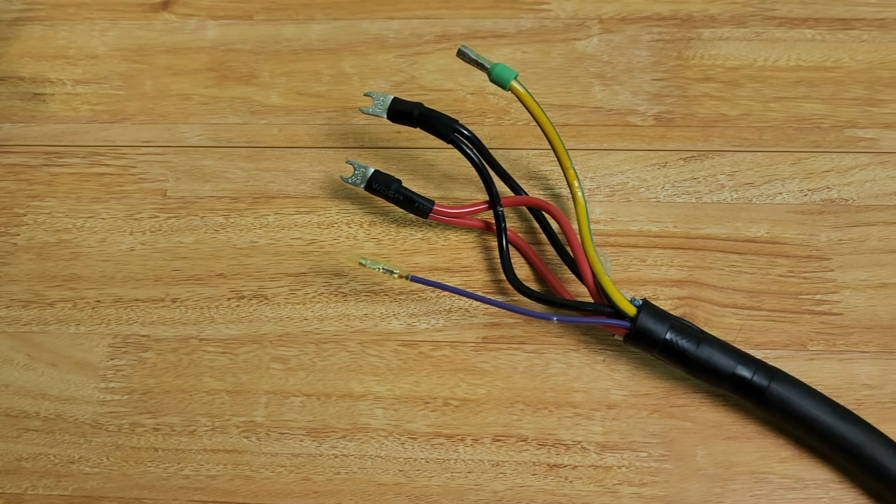So I would guess right now it's set to 6, maybe that's 60 amps. So I'm gonna go ahead and back that off to the 4, which my brain tells me is the 40 amp selection. I will confirm that once I hook everything up. This is only on a 50 amp breaker, so if I do something slightly wrong, hopefully the breaker will protect me while I figure out my mistake.